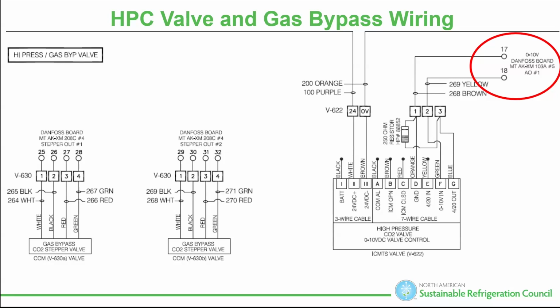Now, sometimes it'll go positive. If I'm close to set point, it's not going to send a signal, so I'm rarely going to see that move. So if I'm suspecting this is wrong, I can simply go into the controller and change the set point so that I can force this valve to drive to a new position, and I will see it go -3, +3, -3, and maybe -4, maybe -5, whatever. But I can see it moving.